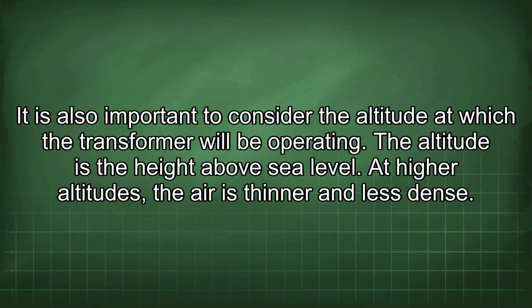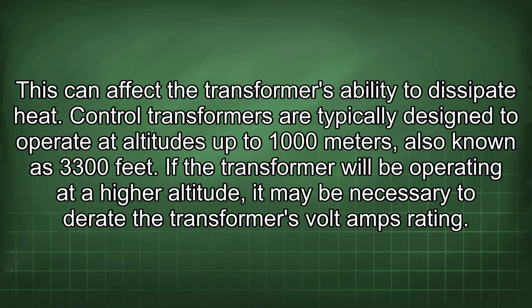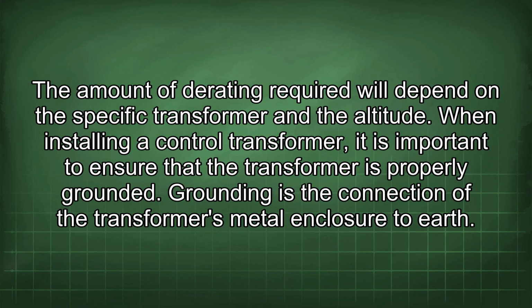It is also important to consider the altitude at which the transformer will be operating. The altitude is the height above sea level. At higher altitudes, the air is thinner and less dense. This can affect the transformer's ability to dissipate heat. Control transformers are typically designed to operate at altitudes up to 1,000 meters, also known as 3,300 feet. If the transformer will be operating at a higher altitude, it may be necessary to derate the transformer's volt-amps rating. The amount of derating required will depend on the specific transformer and the altitude.